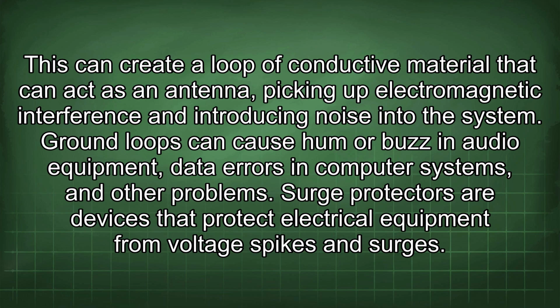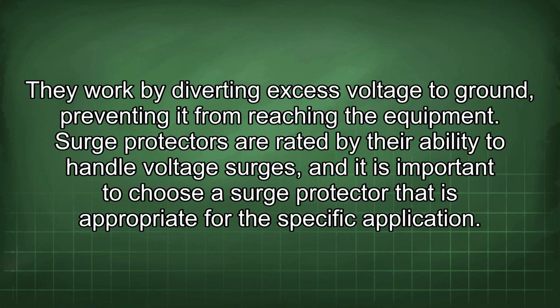This can create a loop of conductive material that can act as an antenna, picking up electromagnetic interference and introducing noise into the system. Ground loops can cause hum or buzz in audio equipment, data errors in computer systems, and other problems. Surge protectors are devices that protect electrical equipment from voltage spikes and surges. They work by diverting excess voltage to ground, preventing it from reaching the equipment. Surge protectors are rated by their ability to handle voltage surges, and it is important to choose a surge protector that is appropriate for the specific application.